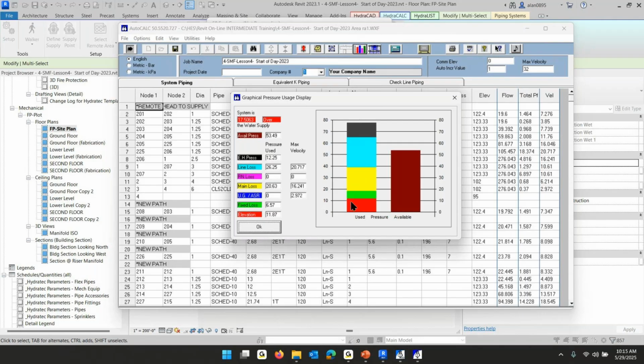Now, I'm going to read into the details a little bit further. The black part of this tall bar is the end head pressure. EHP is end head pressure. And that's 12 pounds. The light blue part is the branch line friction loss, and that's 26 pounds. If I got the branch lines to take a lot less pressure, I could get back pretty much all of that 17 pounds. I don't have any riser nipples. My mains are using 20 pounds. That's this yellow section.